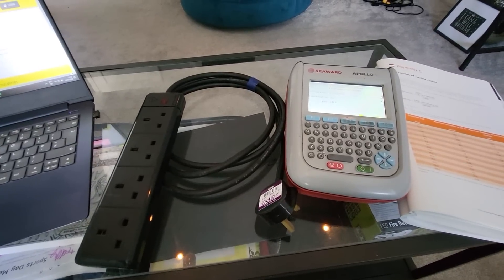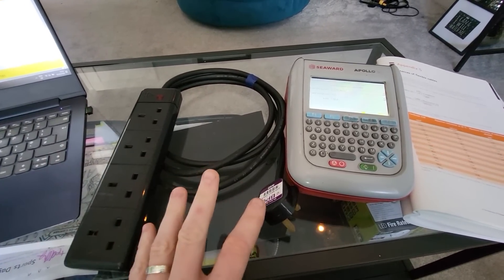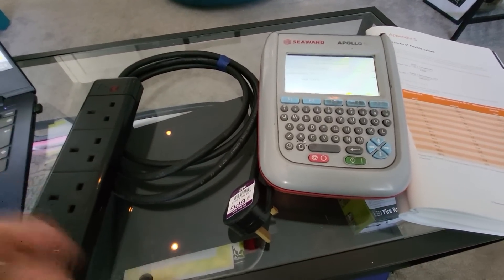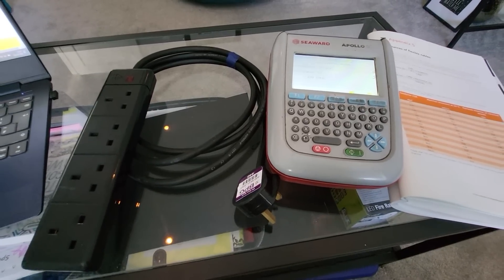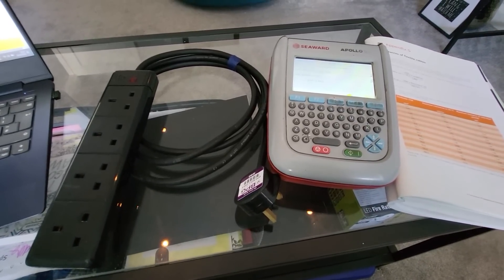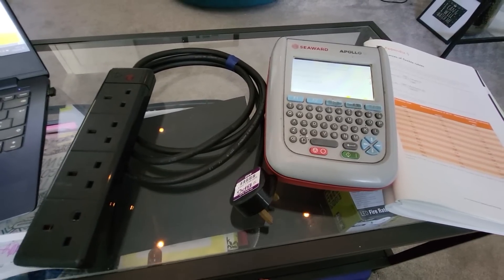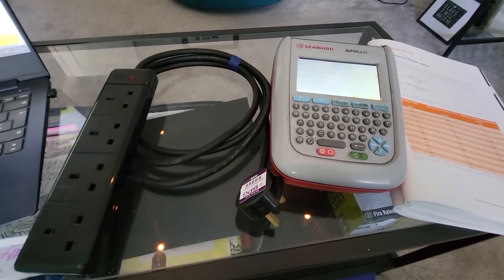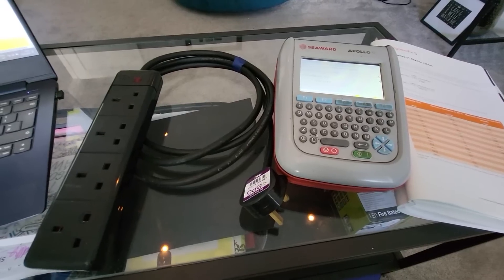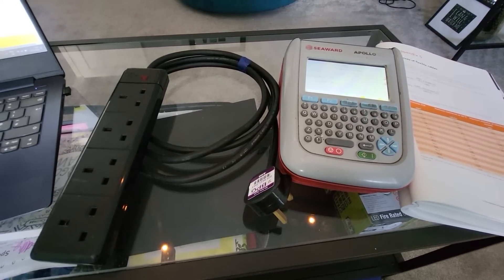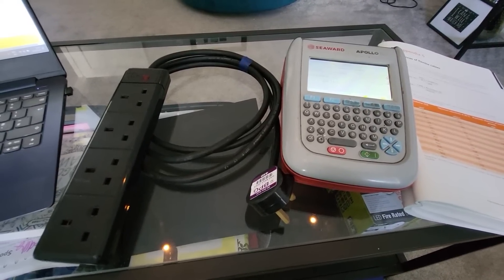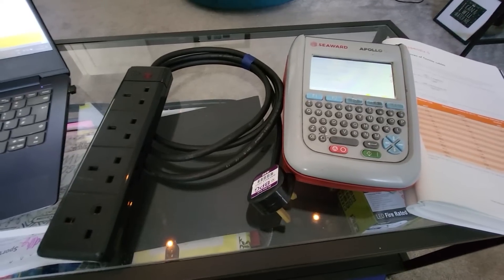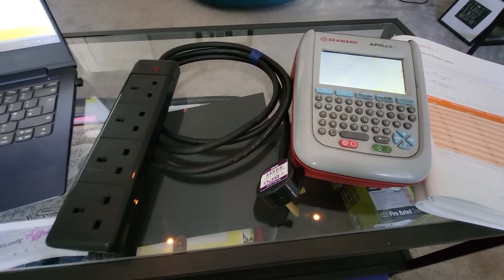And the main thing with that is if you're using a basic entry level machine, like the Prime Test 100, they only have a predefined fail limit of 0.1 ohms. So if you were testing a long extension lead and the reading would come up, say 0.25 or something like that, for example, that's not necessarily a fail.